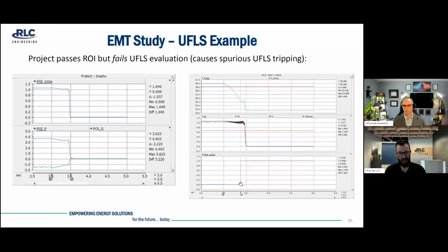Lastly, this is just a flag here at the bottom that goes from 0 to 1 that indicates that the UFLS picked up. And the thing to note here is that, again, the event happens at 3 seconds, the DER trips off at 3.5, but the UFLS picks up before that 3.5. So even though we passed ROI from having less than a 2-second run-on time, we still failed the UFLS and caused nuisance tripping.